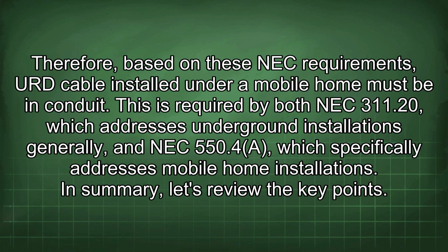Therefore, based on these NEC requirements, URD cable installed under a mobile home must be in conduit. This is required by both NEC 311.20, which addresses underground installations generally, and NEC 550.4a, which specifically addresses mobile home installations.